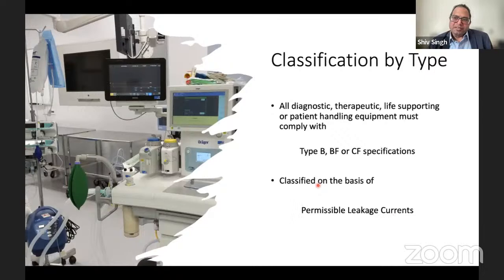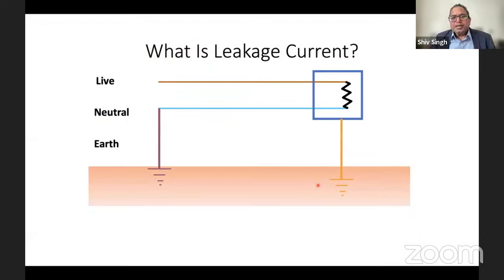So what exactly is leakage current? We've seen that the current flows through the live wire, does work, and returns back via the neutral. If there is a loss of insulation or a disconnection, the current will flow to the body. And if the body is earthed, the current will return via the earth, that is, a protective earth, so that you're not shocked when you touch it. So leakage current is basically the current that does not return via the neutral.